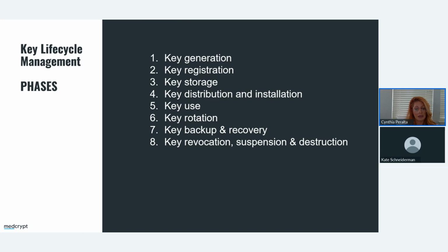The task of key management is the complete set of operations that are necessary in order to create, maintain, protect, and even control the use of the cryptographic keys within your medical devices and their interconnecting systems and environments. Cryptographic keys have a life cycle, believe it or not. So do their associated digital certificates, which we'll get into later. They're created, they live useful lives, and then eventually are retired.